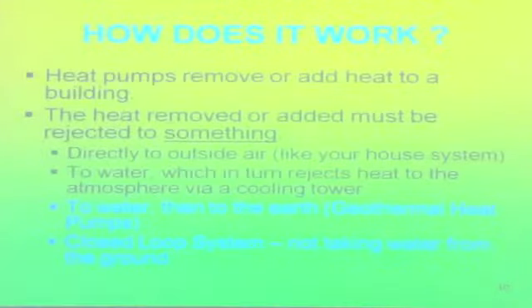Go ahead. One more. So here's the basic principles. You've probably heard the term heat pump. It's a matter of pumping heat from one place to another. Heat's removed or added from something. That's how all of our air conditioners work. We pull the heat out of the building, making the building cooler, and we either take that heat outside, compress it, raise its temperature, so we can discharge it to 100-degree air when it's 100 outside, or in some of the big buildings like this one or all the downtown buildings, we put it into water and we evaporate the water to get rid of that heat.